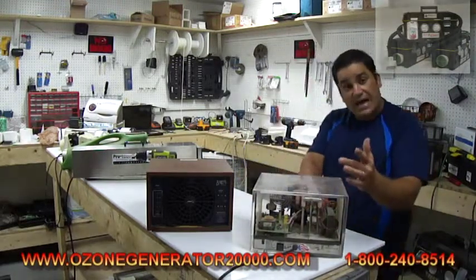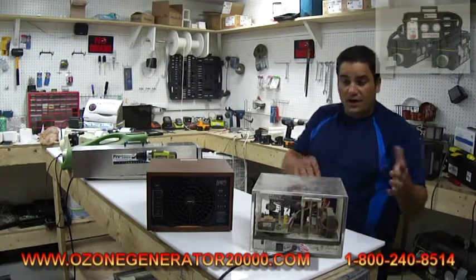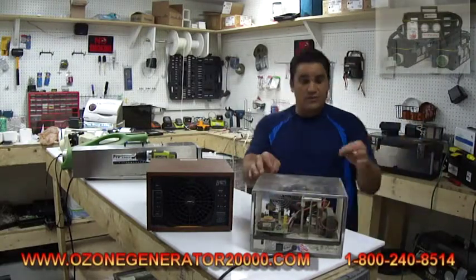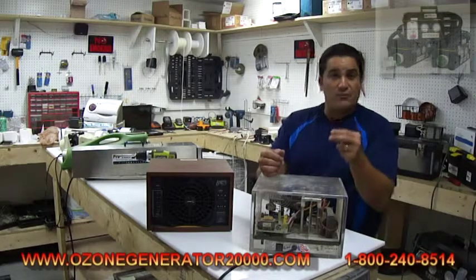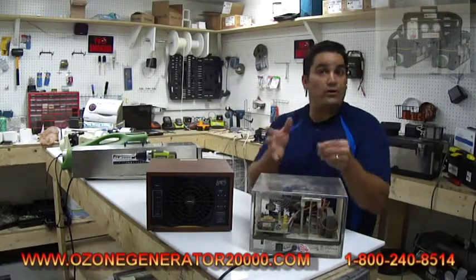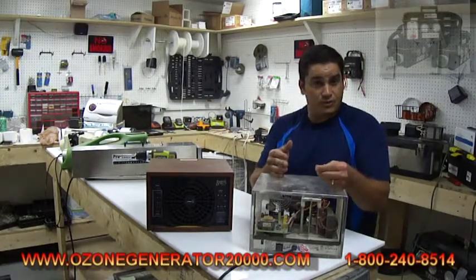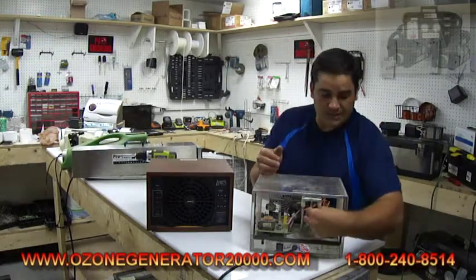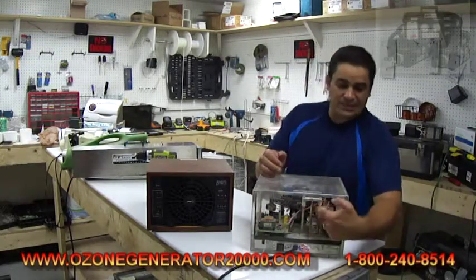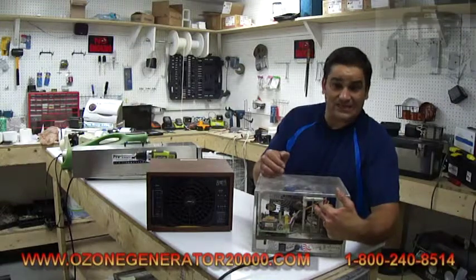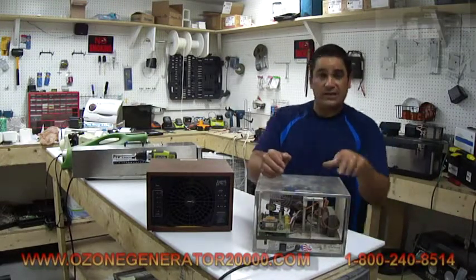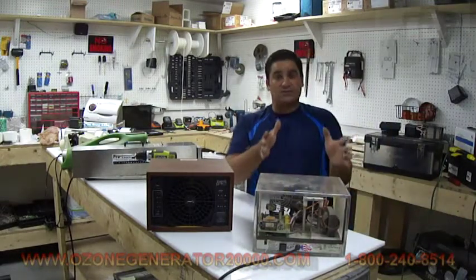The reason they did that was to increase the life of it over our first ozone machine, which twisted the wire in. Remember, I told you the wire eventually corrodes and causes burn through of the dielectric. So to stop that burn through, they just have a tension fitting and stainless steel tabs putting the electricity in. Stainless steel, of course, will never oxidize or rust.